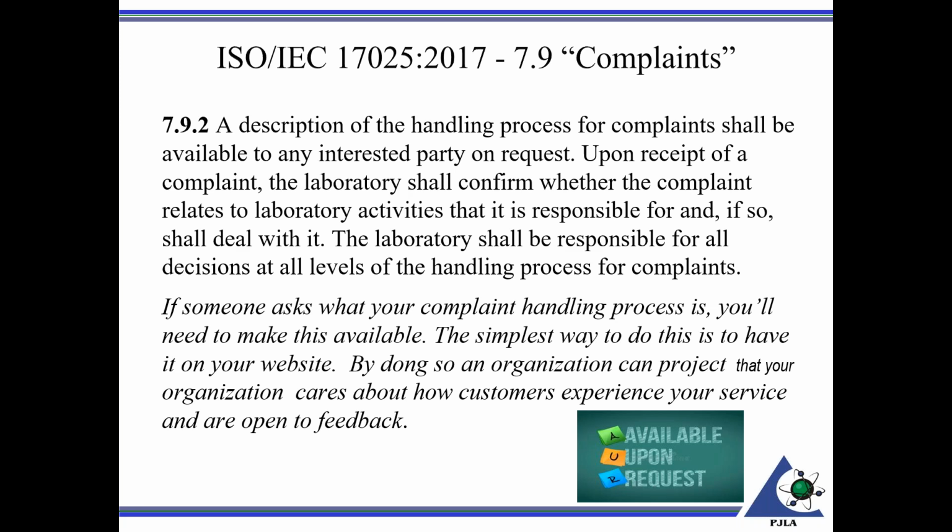Looking at that clause, dissecting it a little bit more: upon receipt of a complaint, the laboratory shall confirm whether the complaint is related to the laboratory activities that it is responsible for, and if so, deal with it. So perhaps the laboratory is a calibration, testing, or sampling organization, and you're part of a larger organization. Perhaps manufacturing, sales, marketing, and other things go on there too. So complaints pertaining to the lab have to be handled by the lab, and the lab shall be responsible for all decisions at all levels of the handling process for complaints. It doesn't go to marketing, it doesn't go to personnel. They can be utilized as resources if the lab needs to, but complaints related to laboratory activities are to be handled by the laboratory.